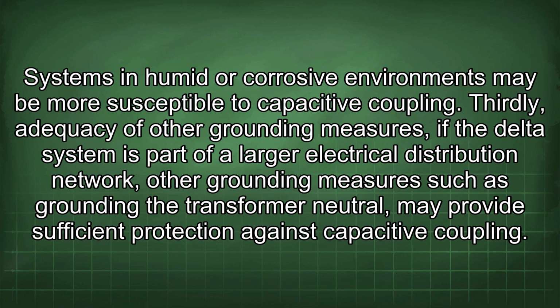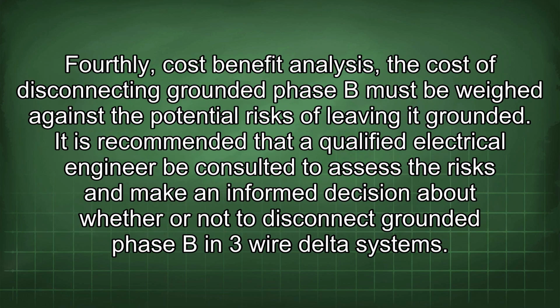Thirdly, adequacy of other grounding measures. If the delta system is part of a larger electrical distribution network, other grounding measures such as grounding the transformer neutral may provide sufficient protection against capacitive coupling. Fourthly, cost-benefit analysis. The cost of disconnecting grounded phase B must be weighed against the potential risks of leaving it grounded. It is recommended that a qualified electrical engineer be consulted to assess the risks and make an informed decision about whether or not to disconnect grounded phase B in three-wire delta systems.